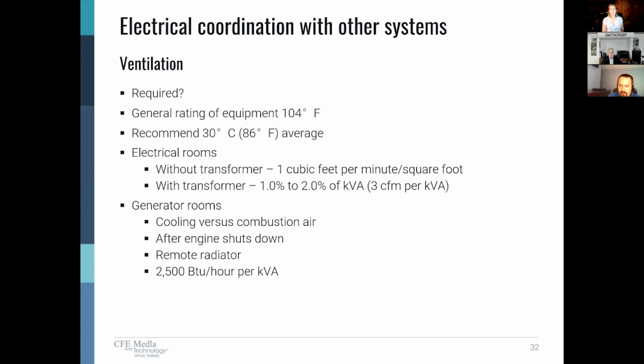Generator rooms are a whole other issue, and there are whole presentations on generator room design and generator room considerations. But you have to understand cooling versus combustion air. The generator has 2 sources of air when we're talking about indoor locations. Those big louvers that are coming in and the big radiator, typically most of that air is for cooling. So for instance, if you were to remove the radiator and put it just outside the room out on grade, you can decrease the louvers significantly in the amount of air you're bringing, because the combustion air is what remains, and the heat radiated off the engine itself, but most of that's going through the radiator.